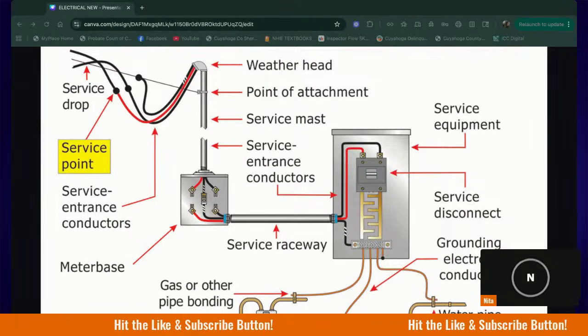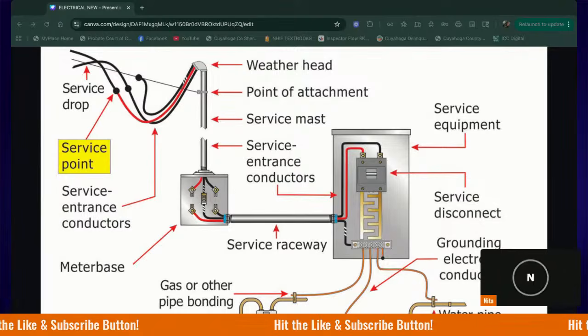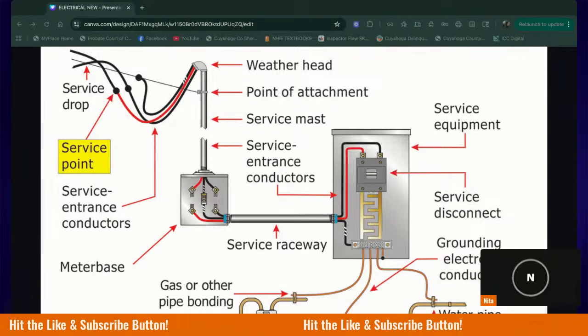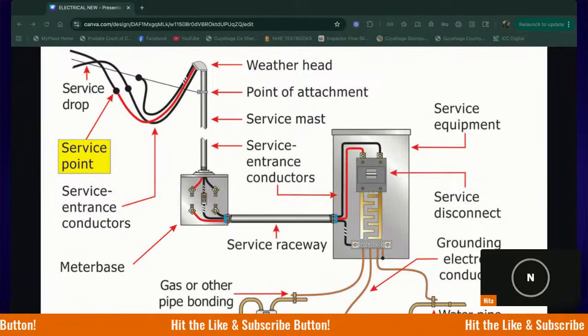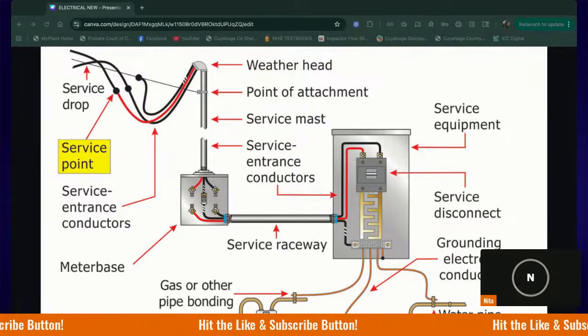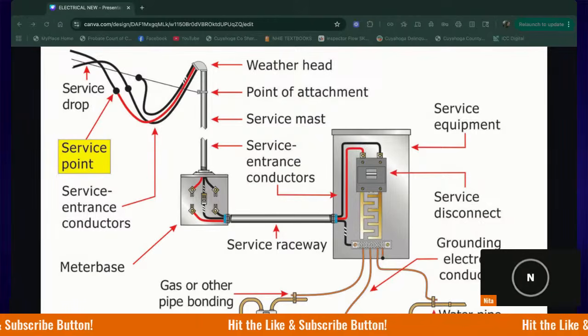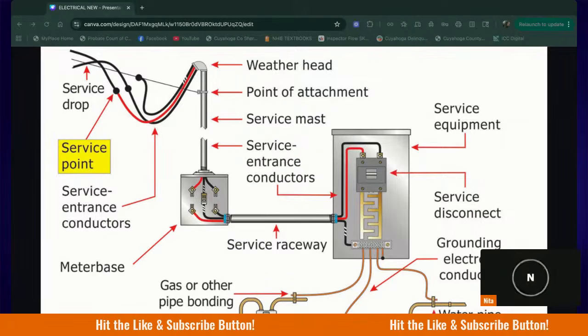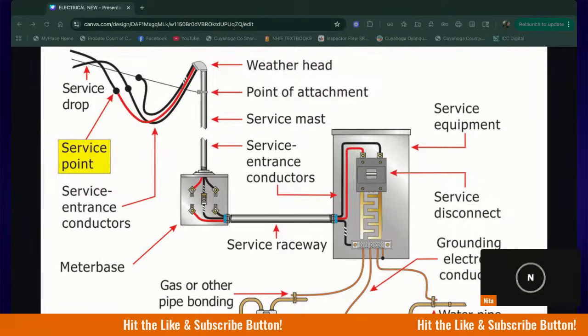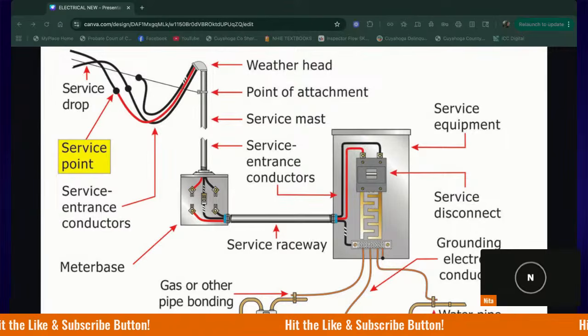Correct. So if we were trying to visually identify the service point, we would look for the splice. It will basically look like 3 wires, and then you'll see like tape. It'll literally look like a real splice, like they have spliced wires together. That point right there is the service point. That is the point that separates the ownership and the responsibility. Is that clear? Yes. Okay, so this is our service point.